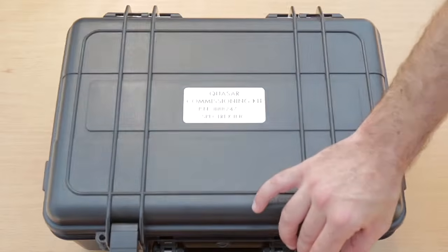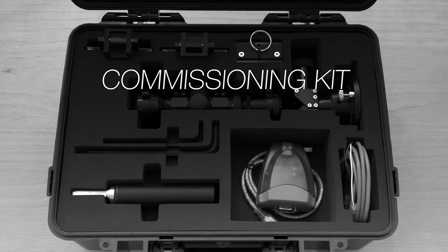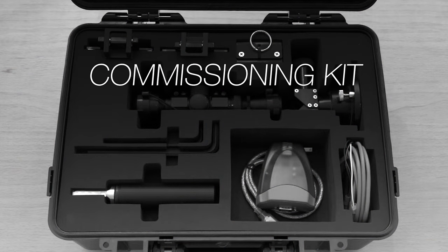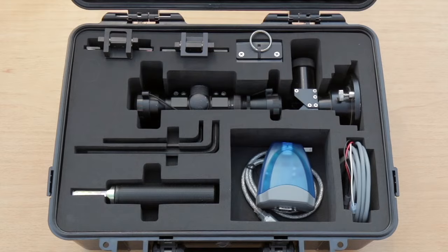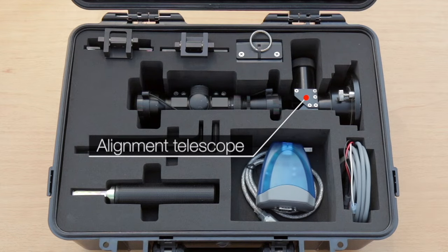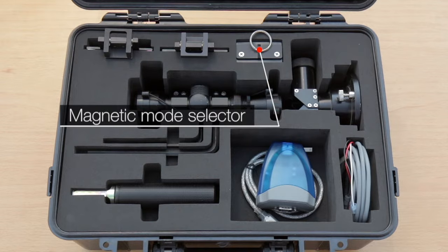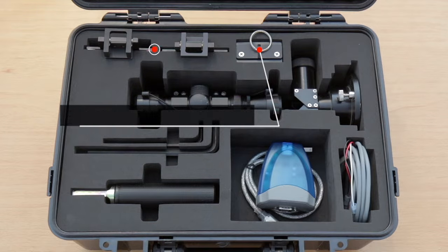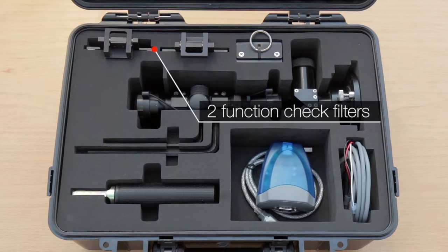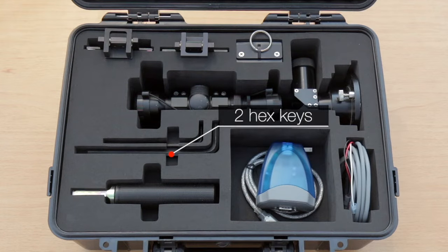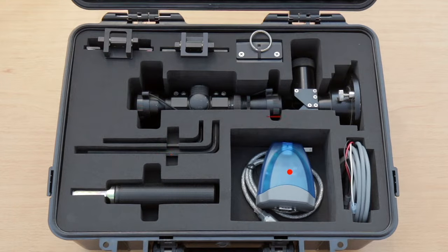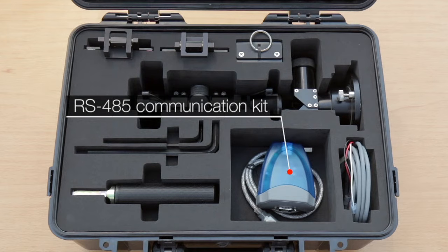The commissioning kit that is provided with the Quasar 900 system contains all the necessary equipment needed to perform the installation. The commissioning kit includes an alignment telescope to facilitate source and detector alignment, a magnetic mode selector for selecting detector operating mode, 2 function check filters utilized for both installation and periodic functional testing, 2 hex keys, one for connecting the unit to the tilt mount and the other for tightening the alignment screws, and an RS-485 communication kit for connecting the Modbus software, which can be downloaded from our website.